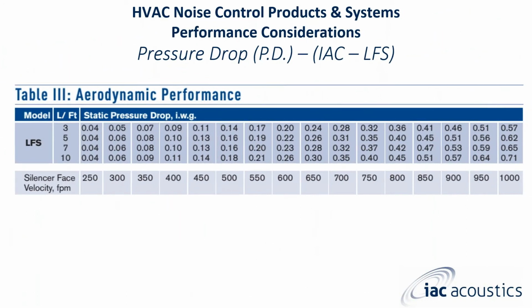One of the nice things within our catalog is a great table, number 3, which is our aerodynamic performance. It shows the silencer face velocity in feet per minute in association with the static pressure drop. Now you see that this is a model LFS. The second column from the left shows 3, 5, 7, and 10. Those are your typical standard lengths. So when you see a 3 LFS or 5 LFS, that's 3 foot or 5 foot, or 36 inches or 60 inches, and so on.